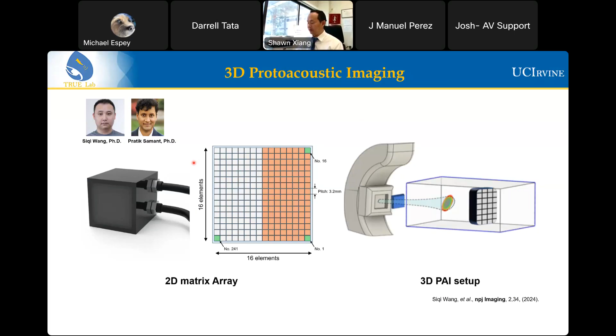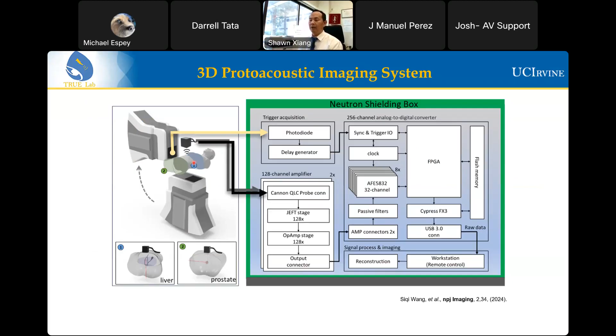So instead of doing this point measurement, we developed a 3D imaging system with a matrix array. We have a 16 by 16 array that gives us this 3D proton acoustic imaging system. We just put it right in front of the Bragg peak. I don't have time to go through the system itself, but basically it's a matrix ultrasound array, and then we built a preamplifier system and data acquisition system, and we can use it for 3D imaging.